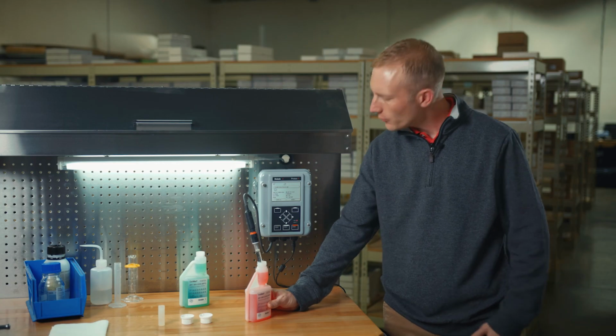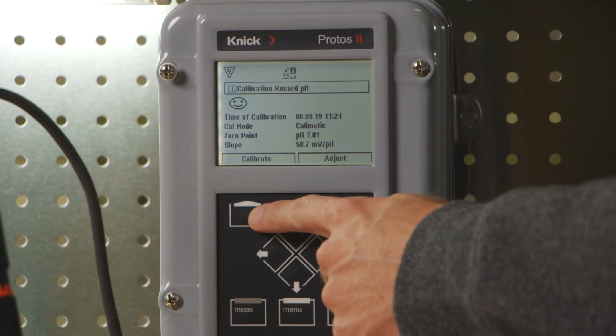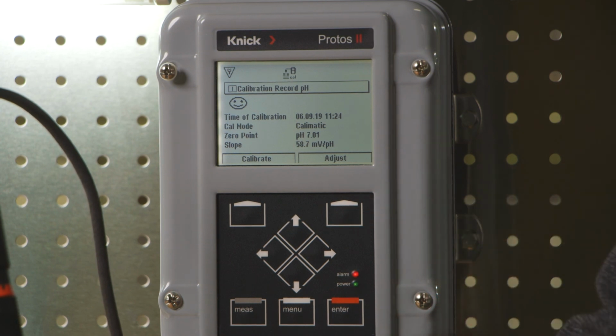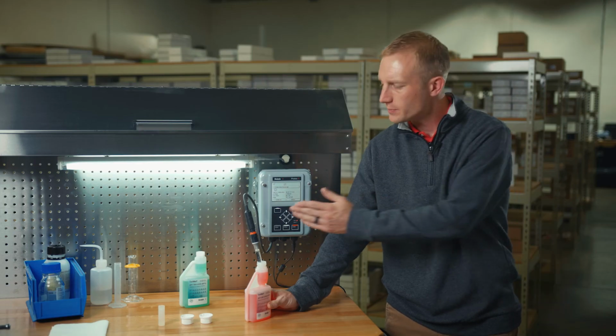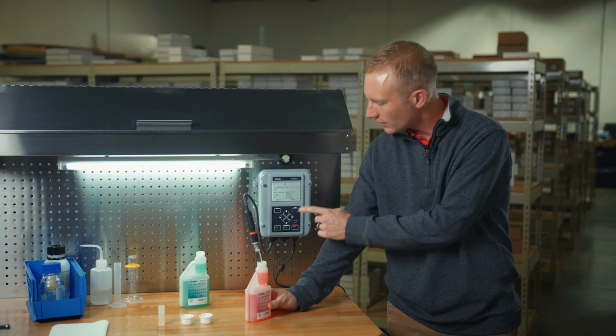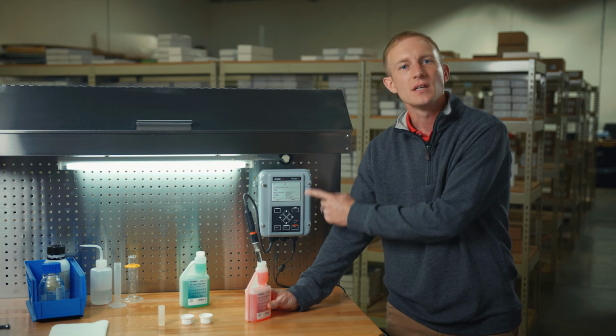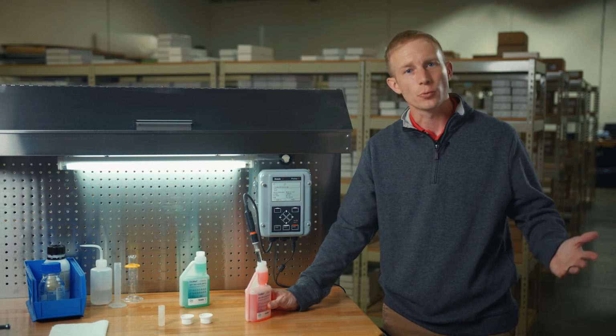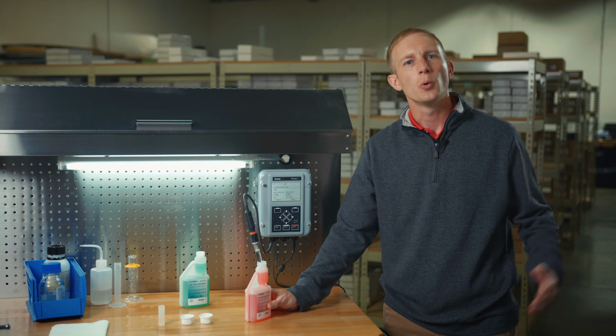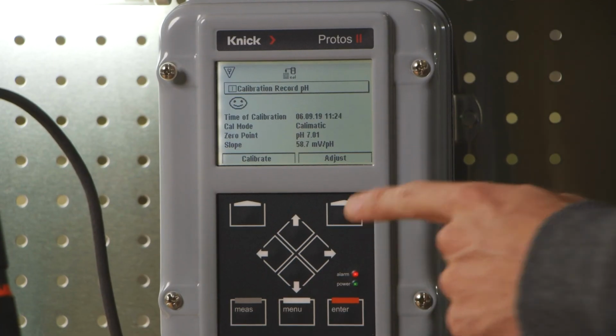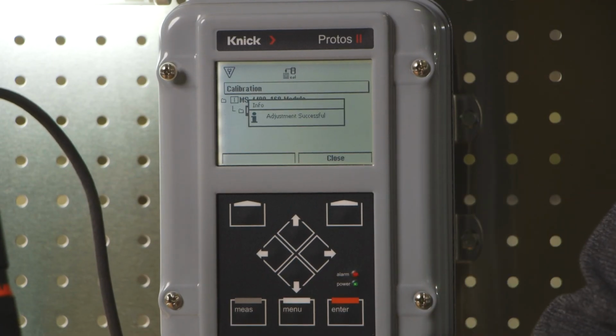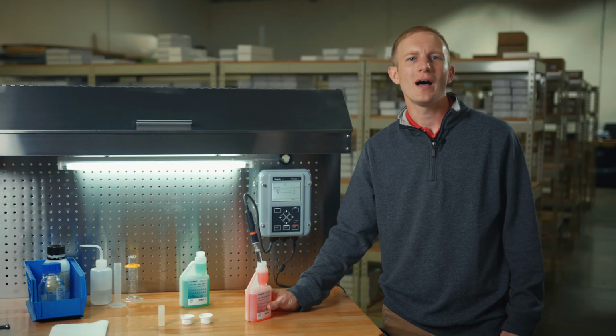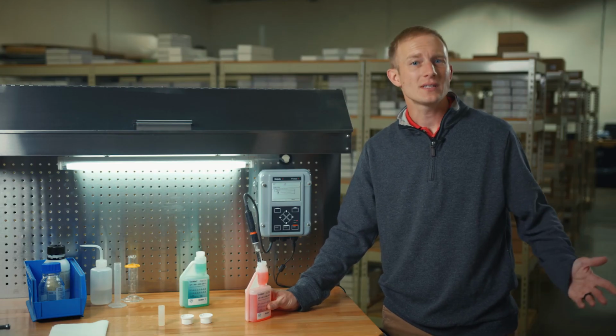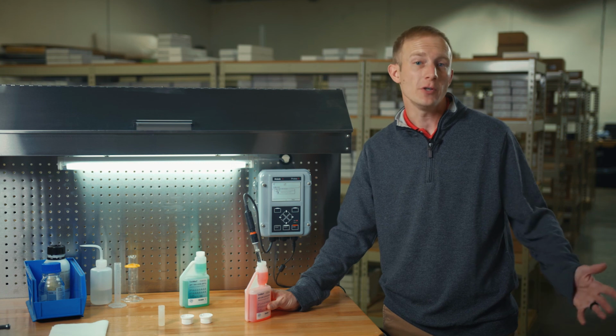Lastly, you can see that we have the ability to select Calibrate or Adjust. It's important to note that no adjustments are made to the sensor without selecting the Adjust button. Selecting Calibrate allows us to restart the process. We will select the Adjust button to finalize the process. We are now ready to go online with our measurement or disconnect our calibrated sensor for future use in the field.